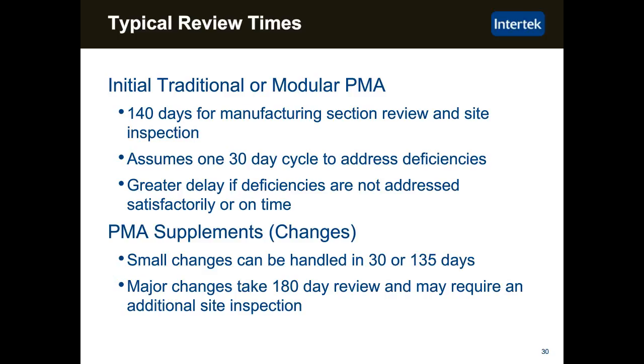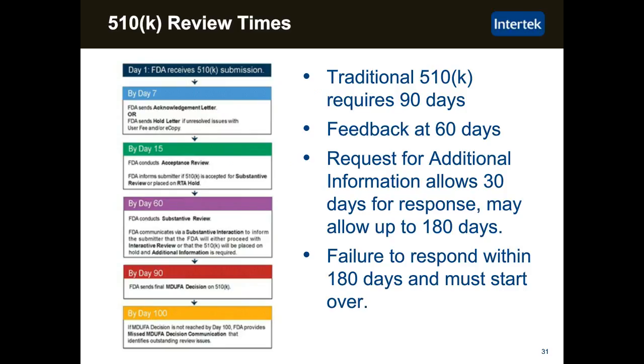Going back into the typical review times, we'll talk a little bit about PMA supplements or changes to a PMA. Small changes can be handled in 30 or 135 days, and major changes will take a 180-day review and may require an additional site inspection. Here's what we're looking at for 510K review times. A traditional 510K requires 90 days.